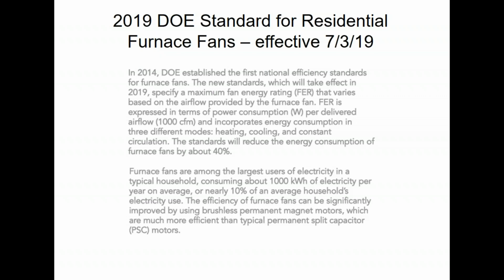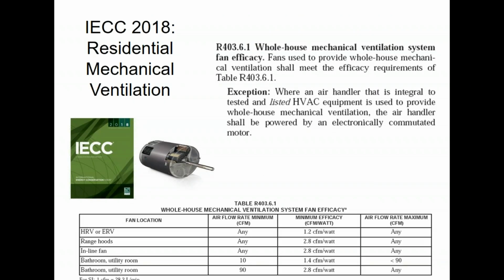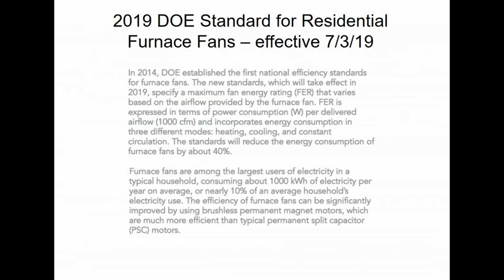I mentioned effective July, I said 4th, it was July 3rd. You have to have ECM motors essentially anyway. So this requirement over here for this ECM motor on a furnace when it's used for ventilation kind of takes care of itself by the national standard anyway. And I think all of you are probably aware of that. We refer to it as FER because that is the efficiency rating metric. It doesn't specifically ban PSC motors or require ECMs, but with the given technology we have for furnaces, the only way to comply is to go to an ECM and stop using a PSC. So that's kind of the way it's been being handled.